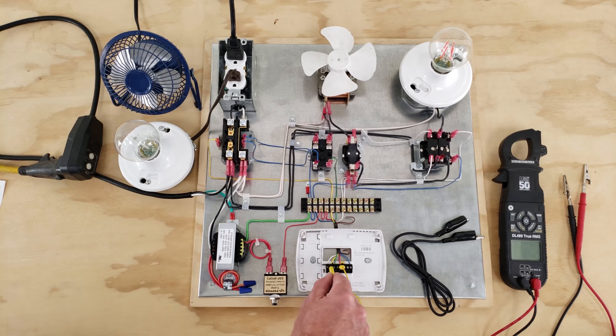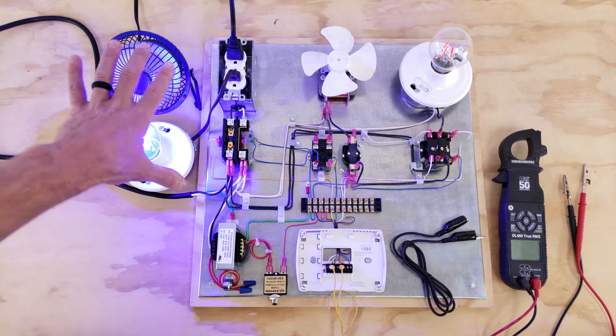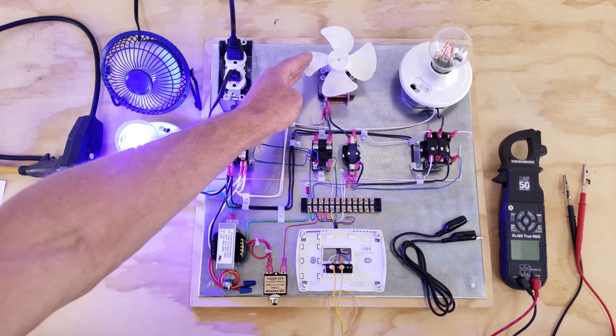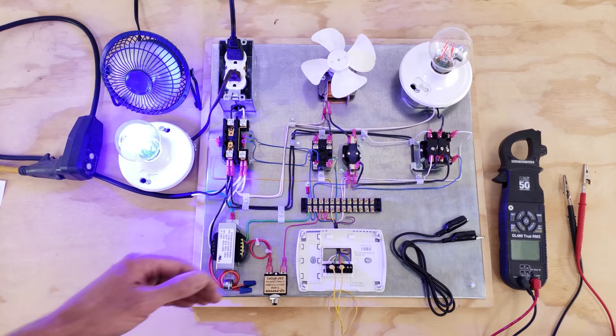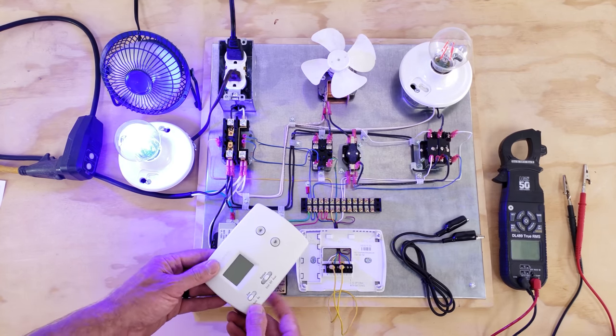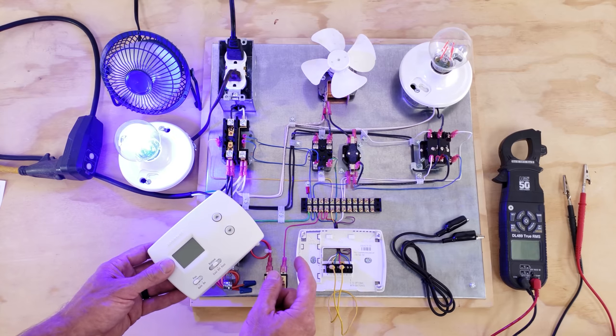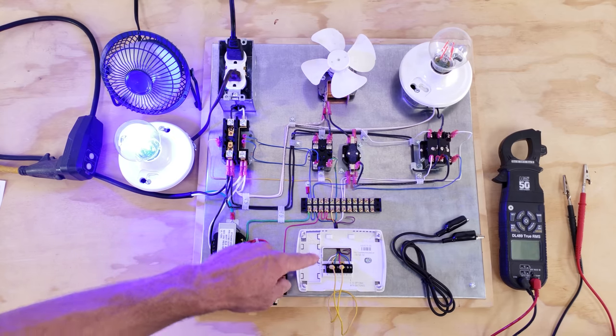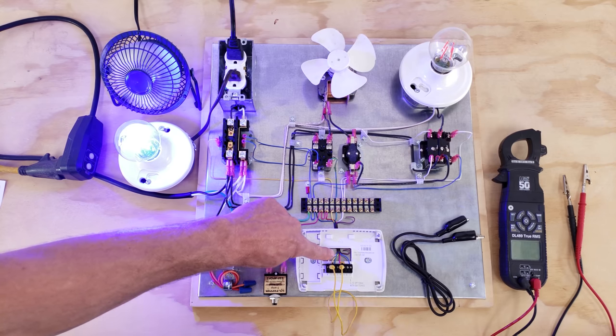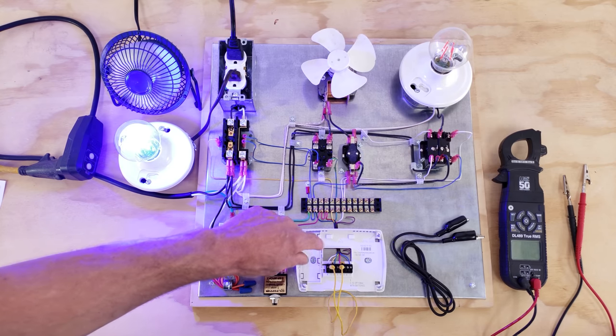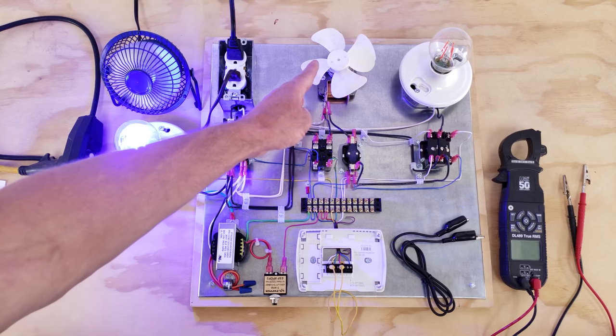And so what's going to happen is we have our outdoor air conditioner turning on, but you see that our indoor fan did not turn on. That's because inside your thermostat during air conditioning mode, R touches both Y and G at the same time. So R touches both the green and the yellow wire right here, and so you have your fan motor running.